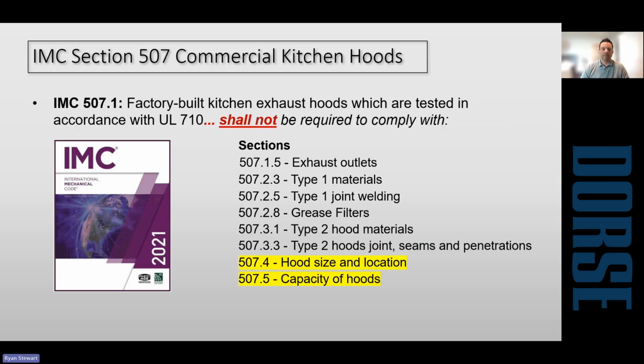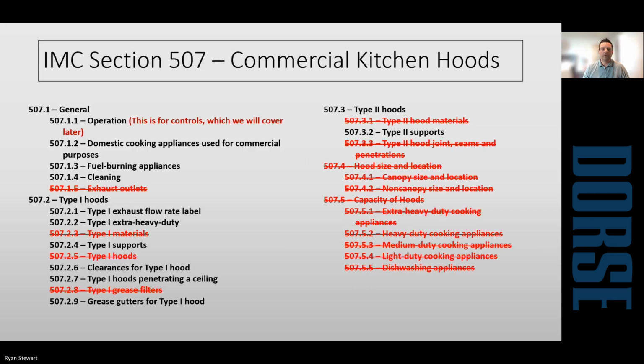So the International Mechanical Code says that any hoods that are built in accordance with UL 710 shall not be required to comply with the following sections. I think the important ones to take a closer look at are going to be the hood size, location, and then capacity of hoods. So this just gives you an outline of how much of Chapter 507 a UL 710 hood is exempt from.